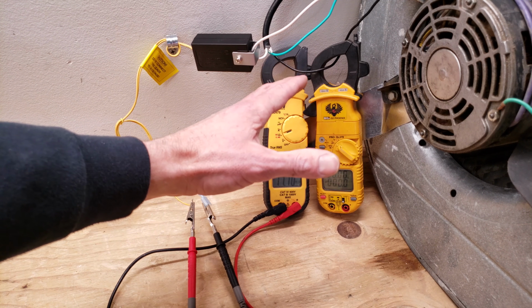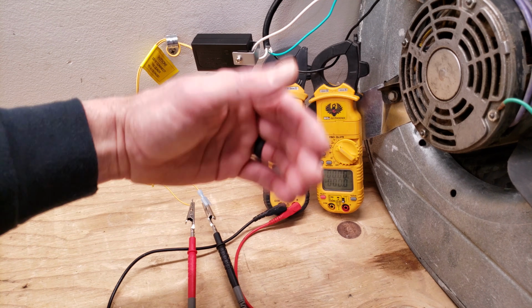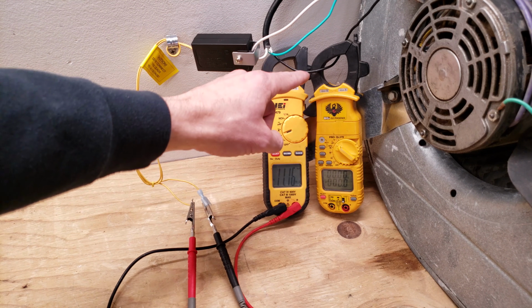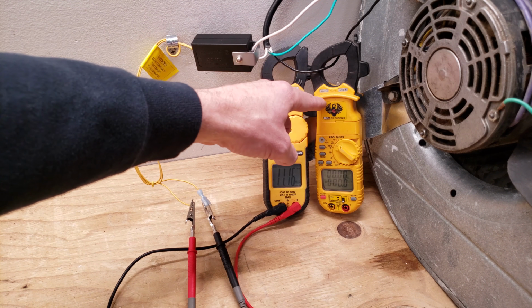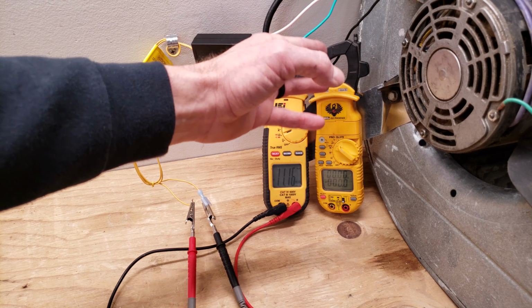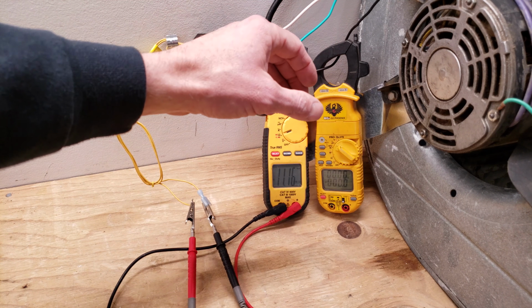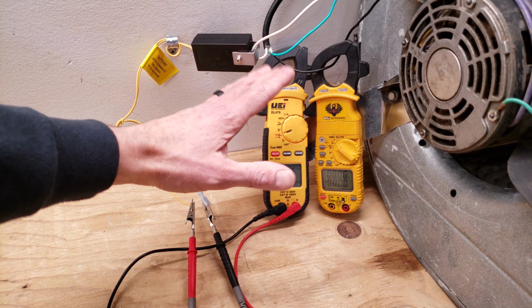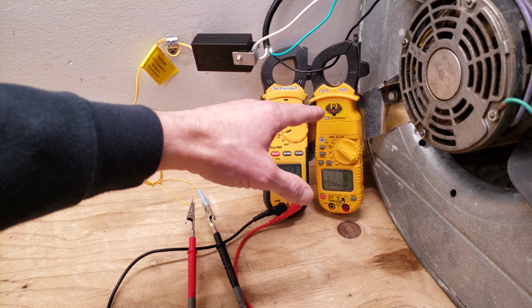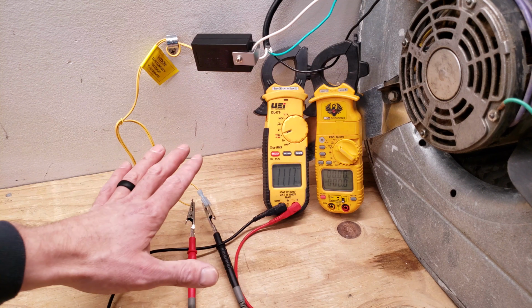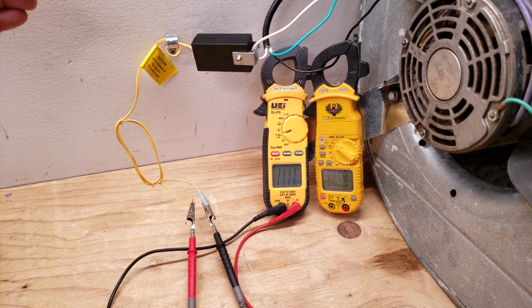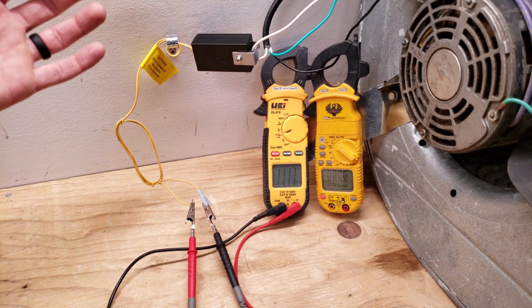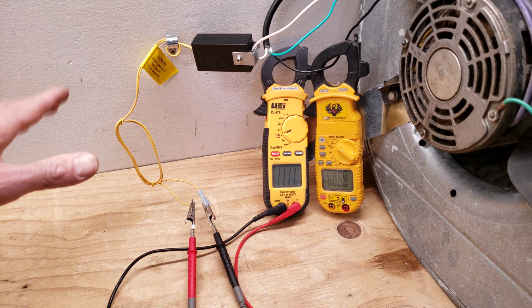And I'm going to tell you that it's best to turn the power off to the furnace or air handler first, and then clamp your amp clamp around the high amperage wire. You don't want to be fiddling around there and there with your hands, because that's dangerous. You don't want to be near amperage. You can set the multimeter in place, you can set all this stuff in place, and then go ahead and turn the power on when your hands are at a safe distance away. So always keep that in mind when checking these.